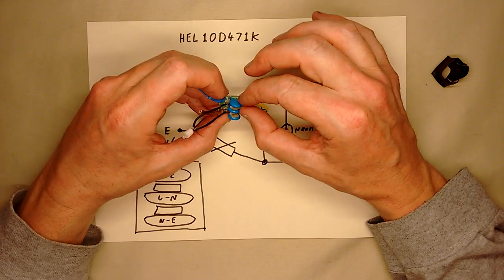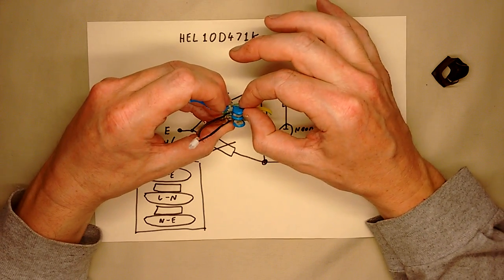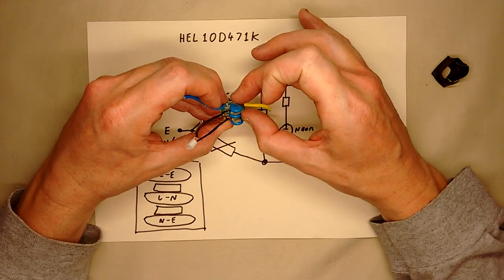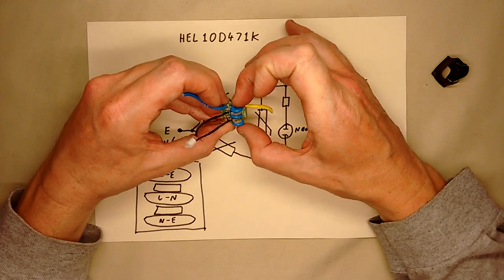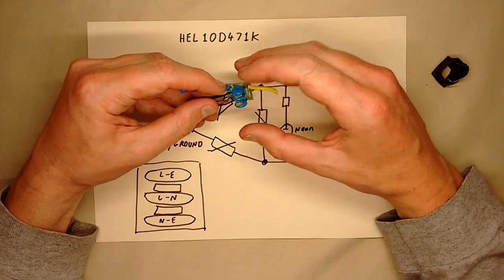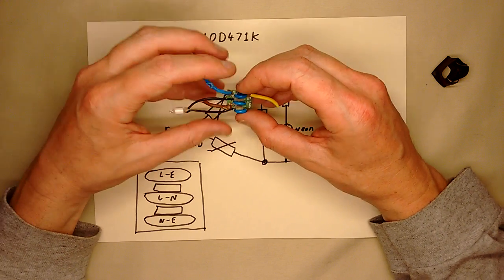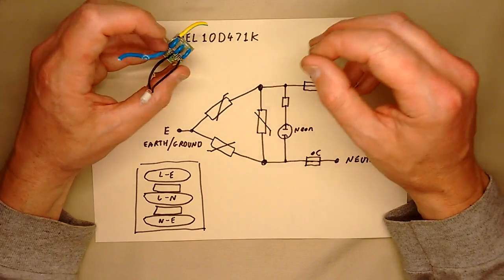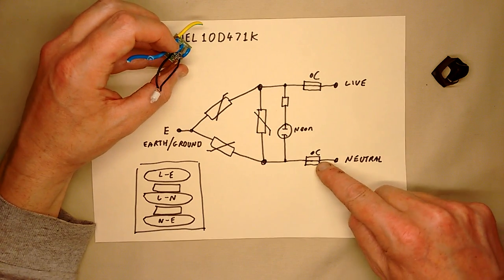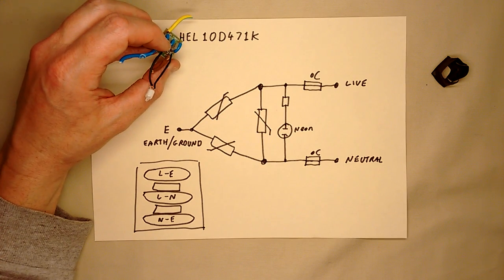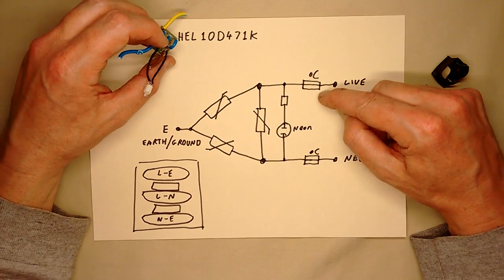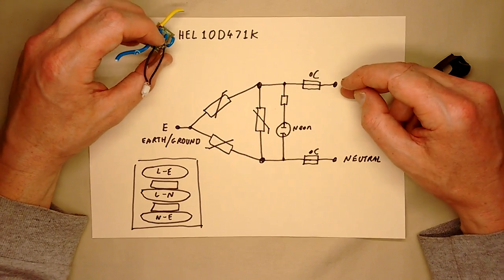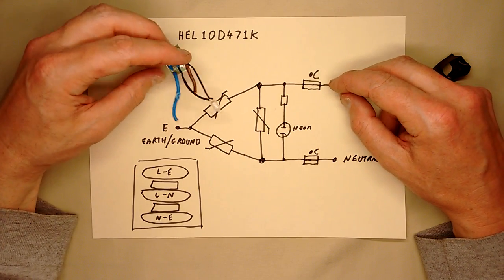Every time they clip a transient, their voltage is exceeded, they gradually break down over time. That results ultimately, when they've really failed, in the heat, and in that case these thermal fuses will blow. These are the thermal fuses here. I wasn't sure the actual symbol for a thermal fuse, so I just drew a fuse and wrote degrees centigrade next to it.